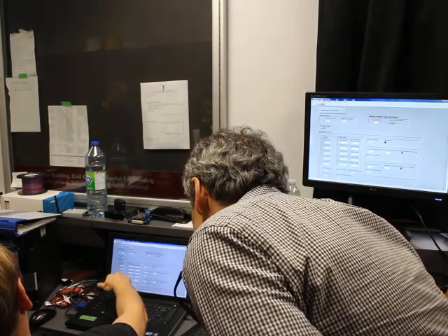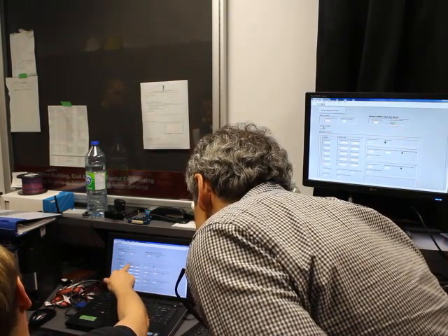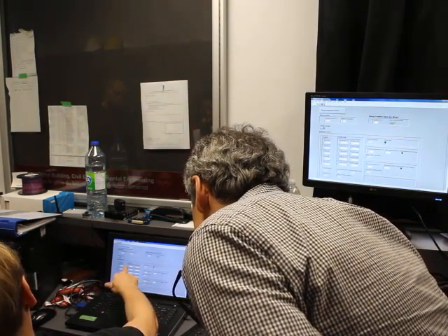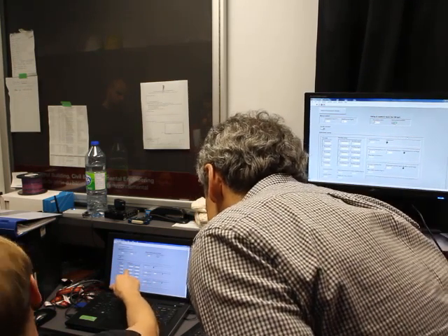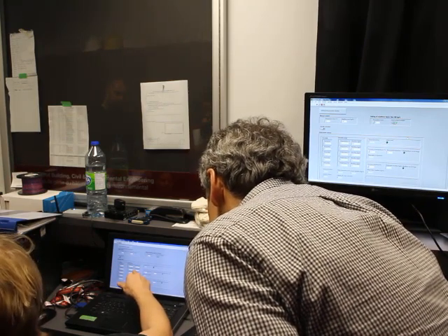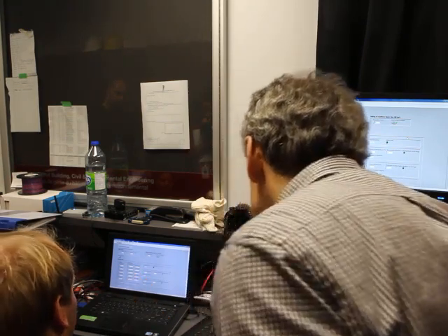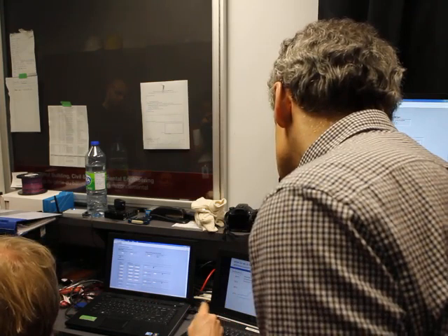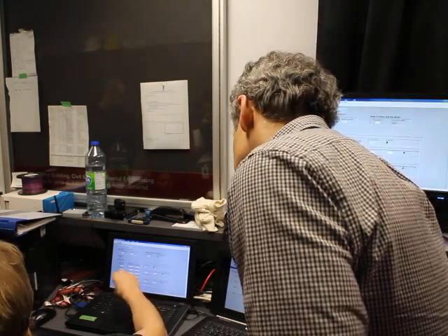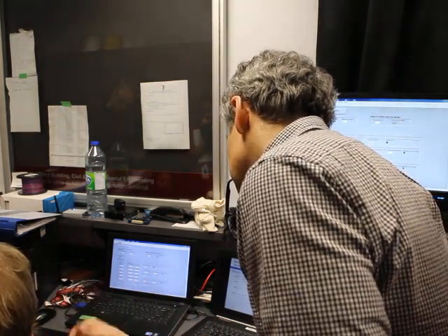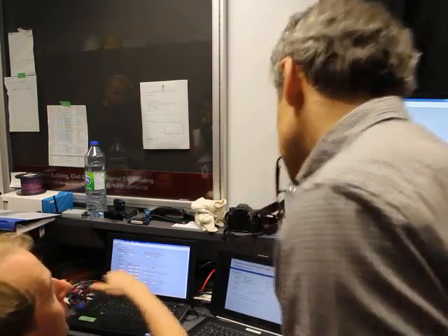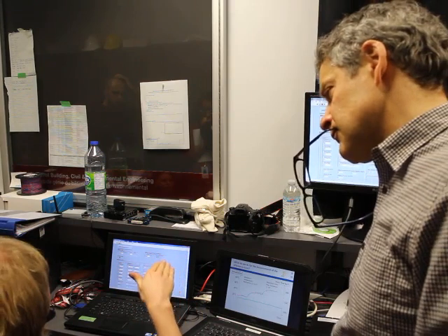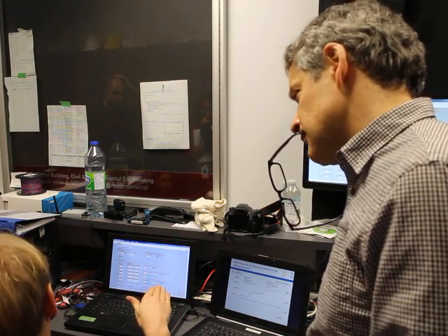And while it's doing that, it's doing 20 degrees, 144. Once it has gone through all that, it goes to the next level, 40 degrees C, also 144 kilograms, because the temperature changes, but not the mass flow. The mass flow will change with the temperature, but the controller will always control it so that it stays at a certain level of 144 kilograms per hour.